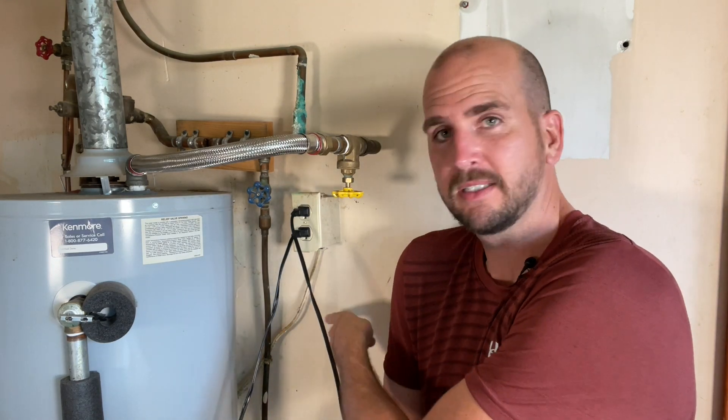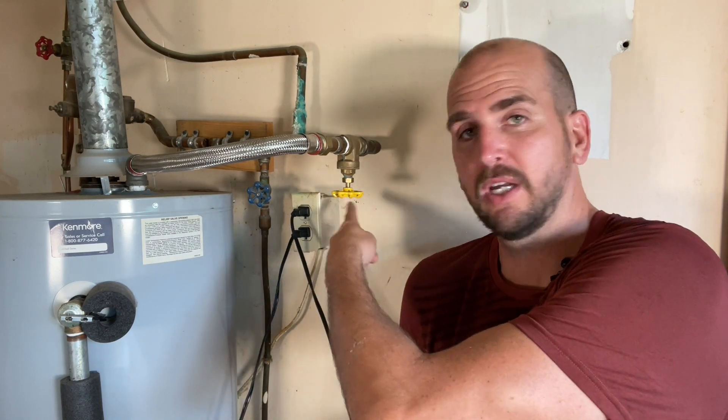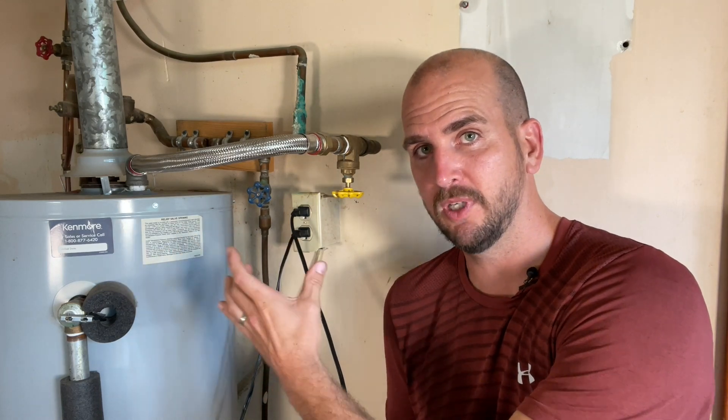Number five — the last issue before the bonus panel location: here we have an electrical box fixed to the outside of the wall. It's not within the wall cavity or ceiling — it's on the outside of the wall, with Romex running externally down and into the floor cavity, then up into the electrical panel. That's a big no. When this was added, it should have been routed through the crawl space, up through the wall cavity, with a hole cut, an old-work electrical box installed, and the Romex coming through that box. That's how you properly add an outlet — not like this.